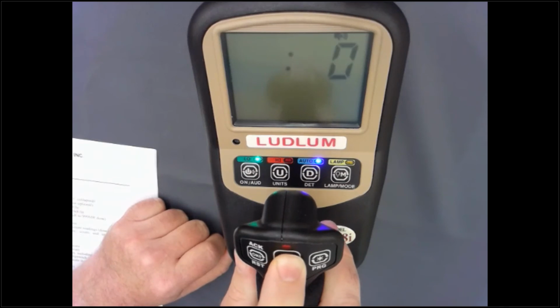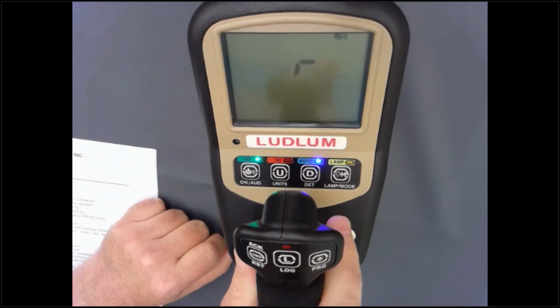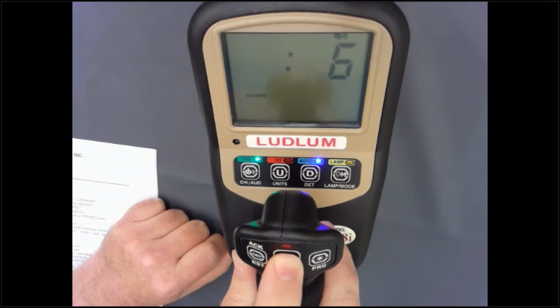We have now changed over to 0. This is going to be an infinite scaler count. 3 more counts. Now we're back up to 6 seconds because that is one of our default counts. Then we can also do 30 seconds, 1 minute, 2 minutes, 5 minutes, and finally 10 minutes.